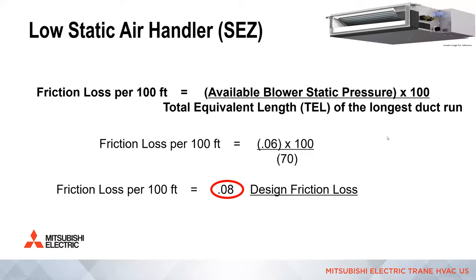And then this next one, with no dampers, how do you balance? Yeah, I did address that, but you wouldn't put dampers in when you're only handling one or two rooms here. As long as the design is correct, you're going to have the right airflow out. When we do a whole entire floor, obviously we need a higher static air handler in order to then put dampers in and overcome those restrictions. So that's when balancing is really important, when you're doing like three or more rooms, right? Thanks, Chris. Yeah, no problem. Thank you for bringing that up. I apologize for missing those.